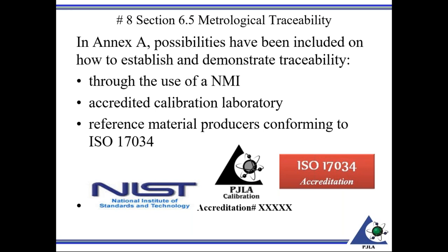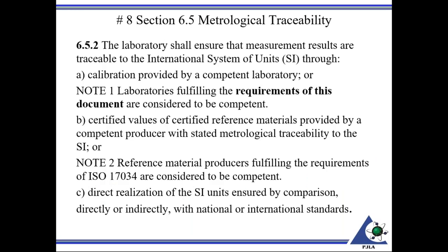Some of you testing folks utilize reference material. One way to assure traceability is going through an organization that is 17034 accredited. These are all ways to assure traceability as specified in Annex A. So there's the requirement there. The laboratory shall ensure measurement results are traceable to the International System of Units through calibration provided by a competent lab. There's a note that basically states a lab fulfilling the requirements of 17025 is considered to be competent.